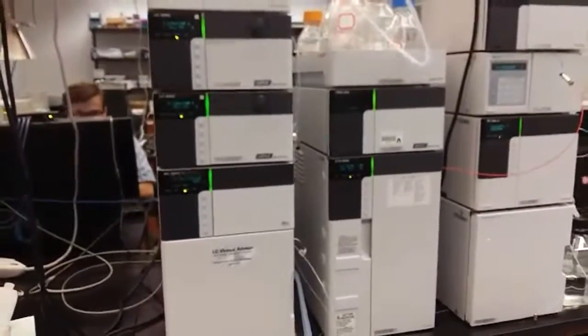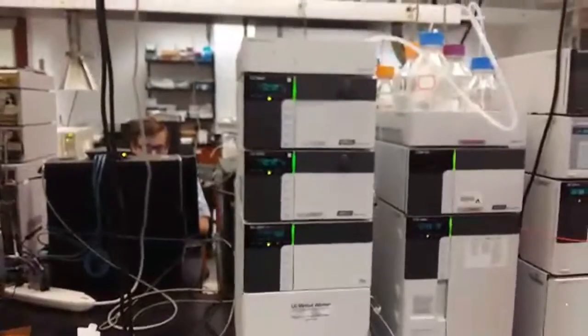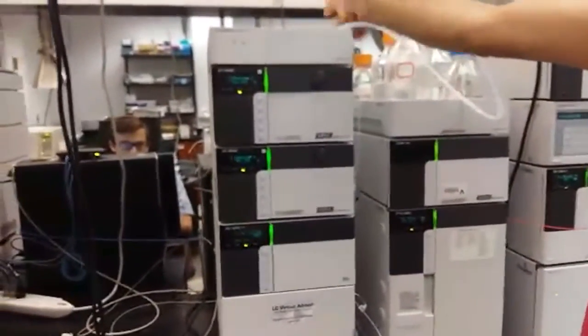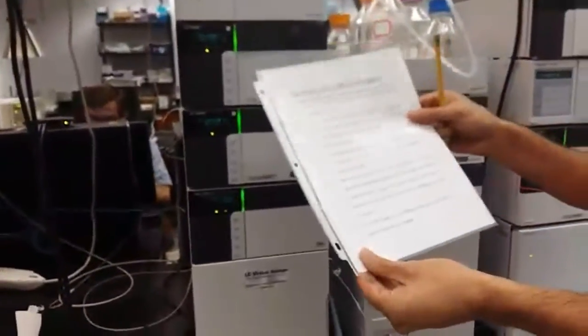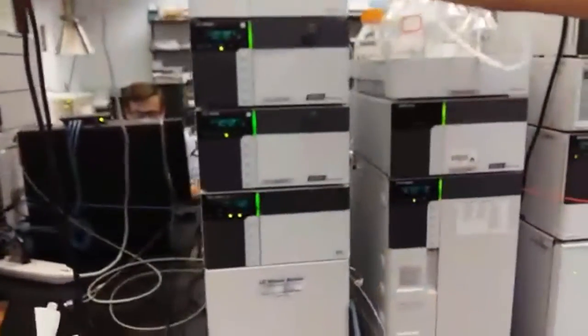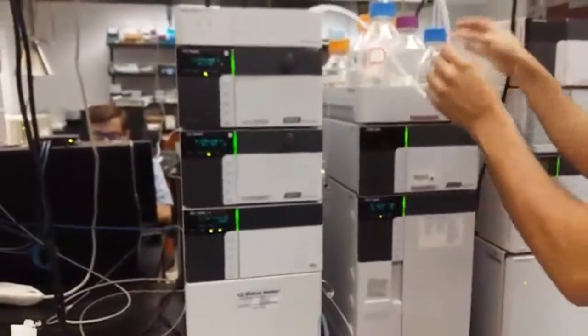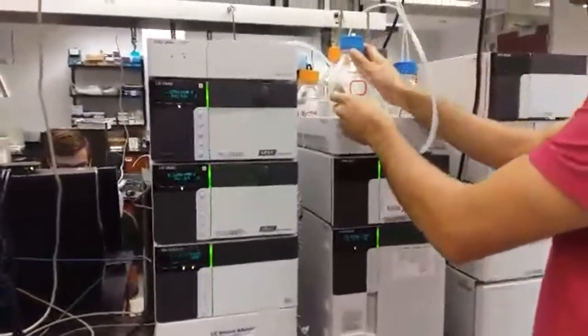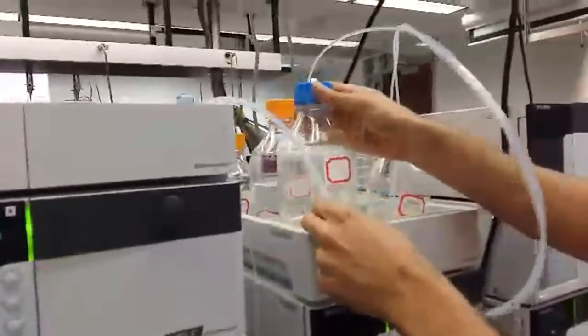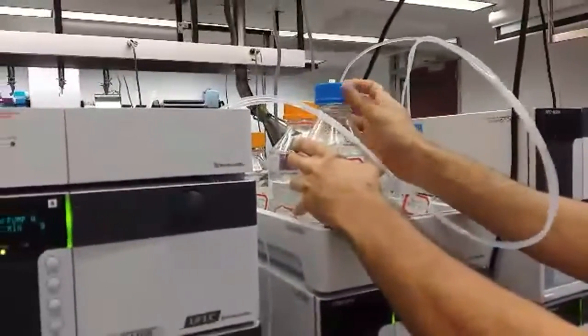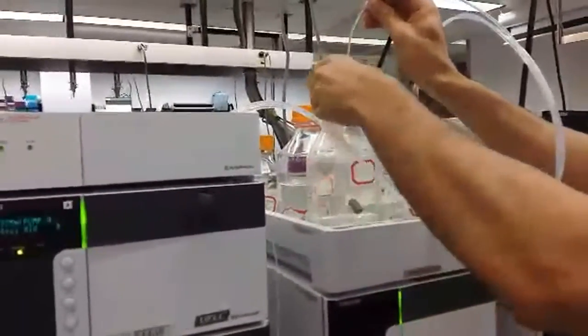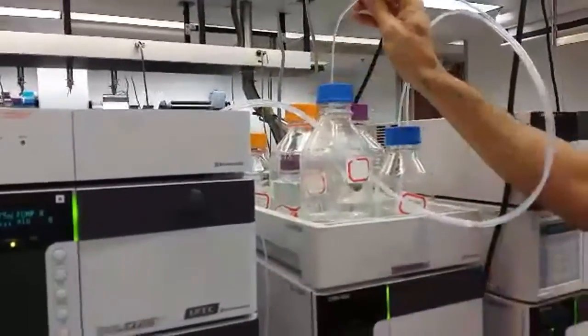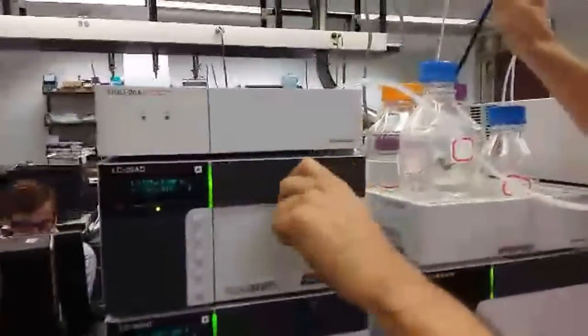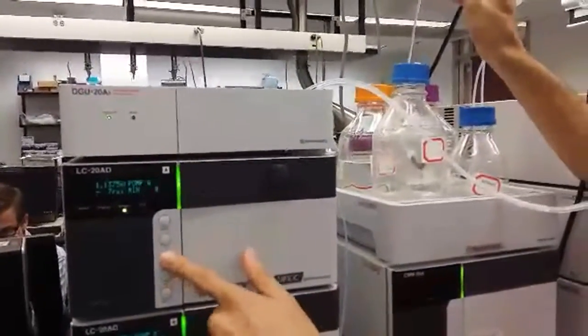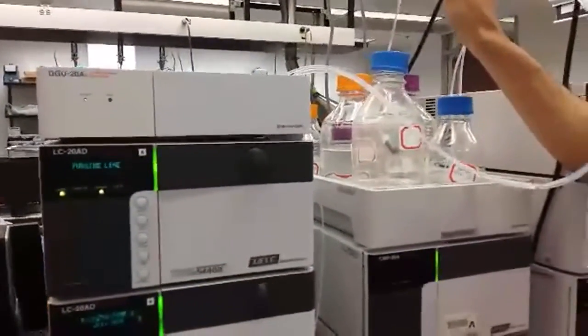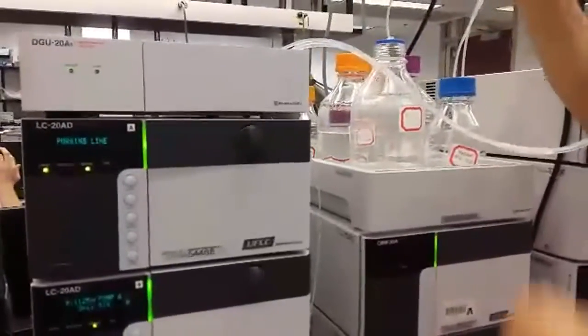Then the first thing you have to do after this is purging the pump. The instruction for purging the pump is in this sheet. You can use it, but I'm going to describe it here. First I'm going to purge pump A. A stands for aqueous, which is the water. I will take out the tube from the water reservoir. You can see it's not in the solution. I will open this knob and push the purge button. Wait to see some bubbles in the tube.